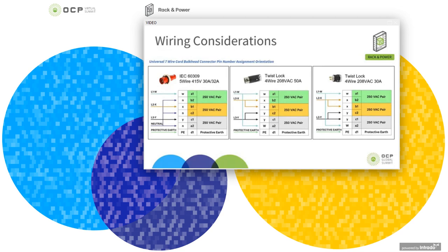So what happens in there is you can see on the first instance here, the far left, where we've got a 32 amp Y input, we've taken that neutral, and we want that neutral to be sourced against every pair. So we take that neutral and we splice it and split it into three different neutrals so that it can occupy three of the pins on that seven pin connector. The other three are comprised by the phase conductors, here represented as W, X, and Y.